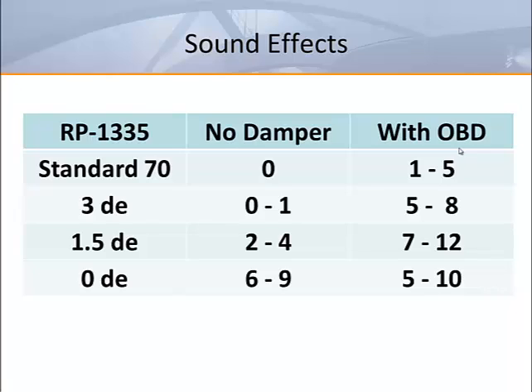This chart shows a broad summary of the research project RP 1335 conducted at the University of Nevada, Las Vegas. The transaction was presented to ASHRAE in Chicago. Multiple types of outlets from 3 manufacturers were tested per ASHRAE Standard 70, plus with a hard duct and a flex duct at 3 diameter equivalents, 1.5 diameter equivalents, and 0 diameter equivalents, and fed with a 90-degree elbow at that height. All combinations were tested with and without an opposed blade damper at the diffuser inlet. The damper was in a wide open position.